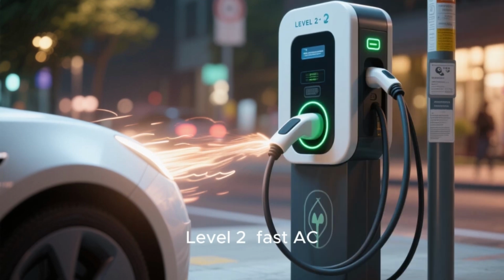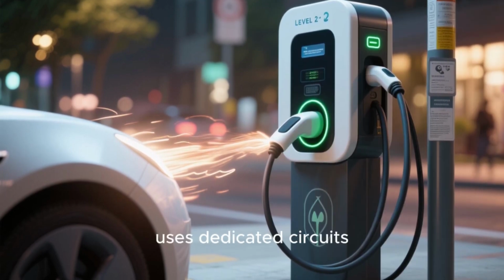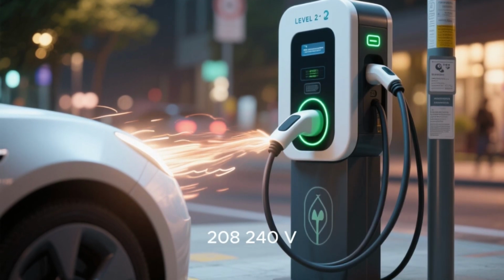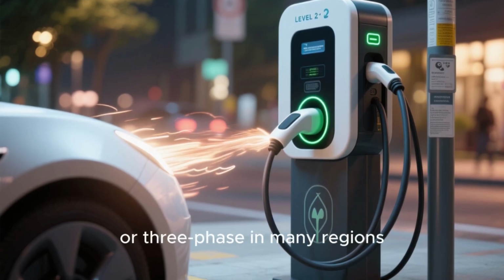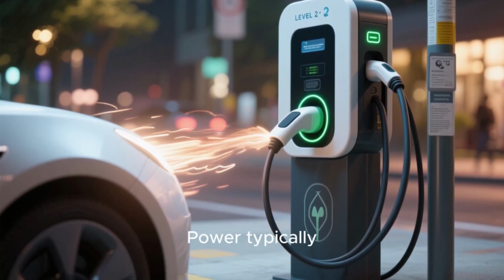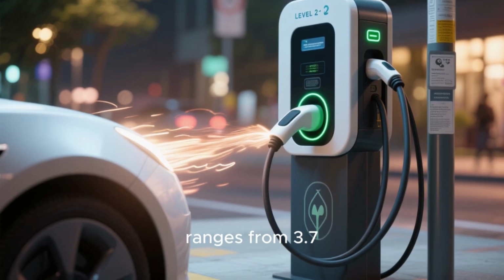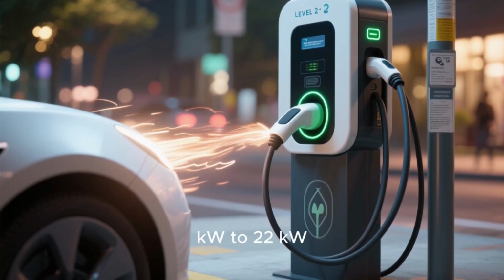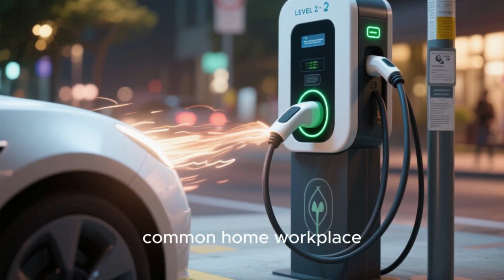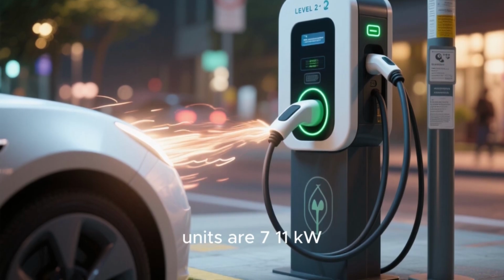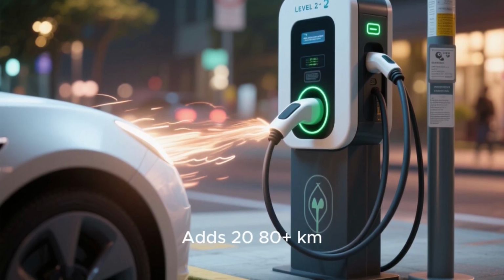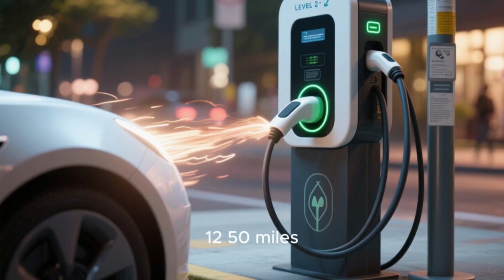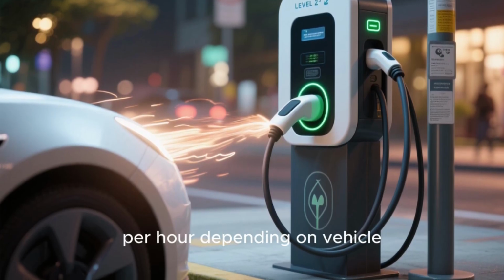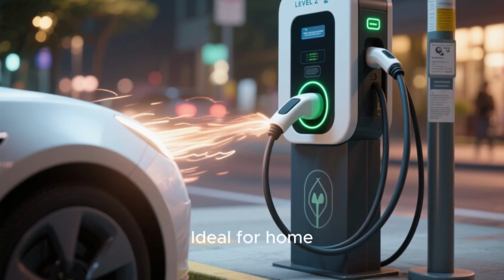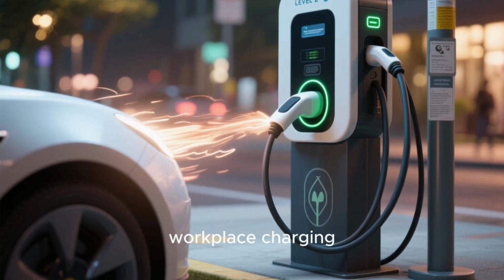Level 2, fast AC, uses dedicated circuits, 208 to 240V single-phase or three-phase in many regions. Power typically ranges from 3.7 to 22 kilowatts, with common home or workplace units at 7 to 11 kilowatts. This adds 20 to 80 plus km, or 12 to 50 miles per hour, depending on vehicle and power level. Ideal for home overnight charging and workplace charging.